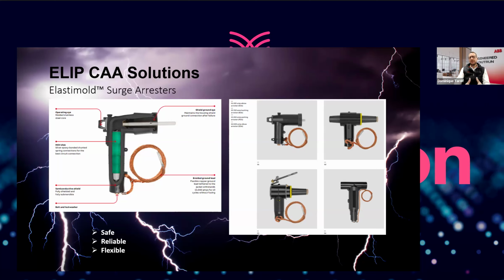What we offer is called surge arresters, still using that elastomer technology. It's dielectric, but basically acts as a bleed out valve. If there's a lightning strike or excessive power surge, it allows that energy to bleed out of the system relatively quickly. Replacing the surge arrestor itself is a quick and cheap way to get back online, as opposed to replacing the transformer or the capital equipment servicing multiple locations. It's one of the ways we're able to get the grid back on a lot more quickly.